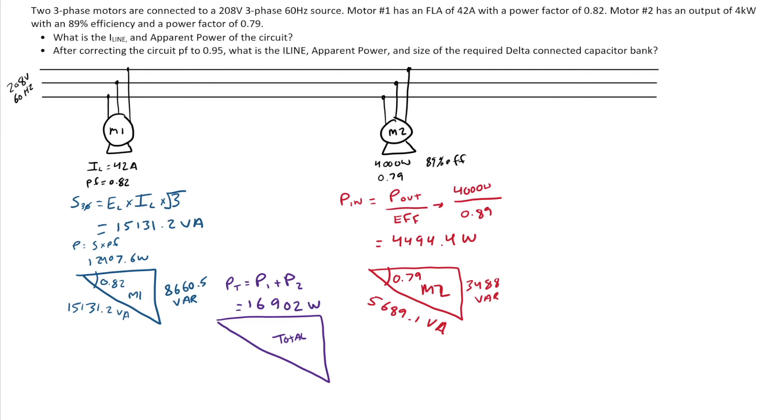Same thing with my VARs. They're both lagging reactive VARs. So I just go 8,660.5 plus 3,488. That gives me my total Q. So Q total, my reactive power total, Q1 plus Q2. In this case, I end up with 12,148.5 VARs.